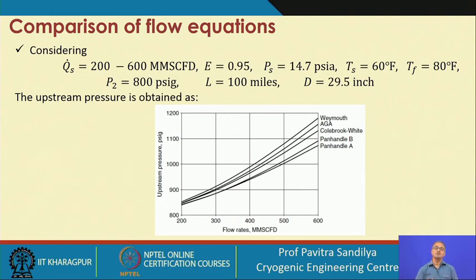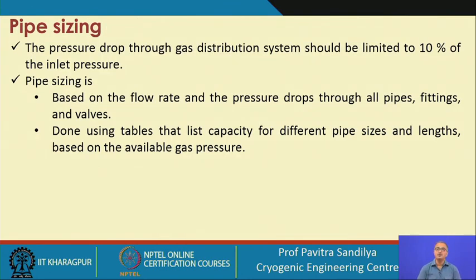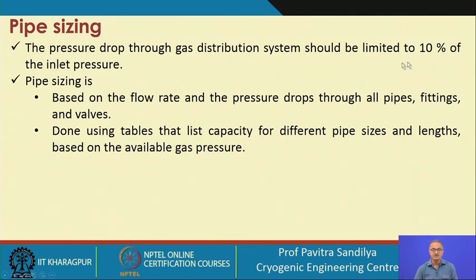Generally, we may use the Weymouth equation for compressor selection. After knowing the pressure drops, we proceed to pipe sizing — deciding what diameter of pipeline to choose for a given length. The pressure drop in the district gas distribution system should be limited to about 10% of the inlet pressure. This is the thumb rule we follow to design the pipe size.